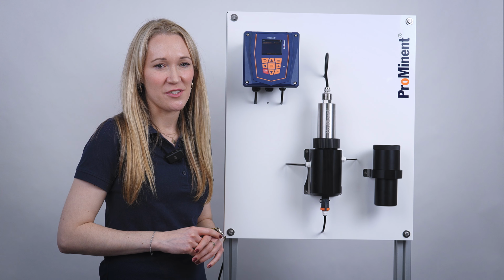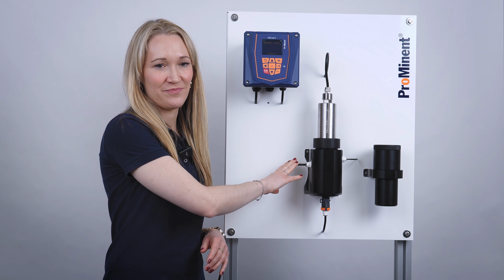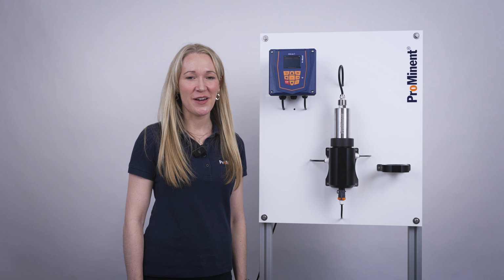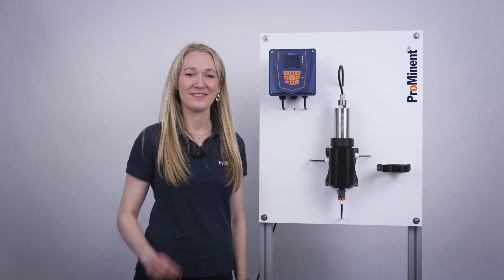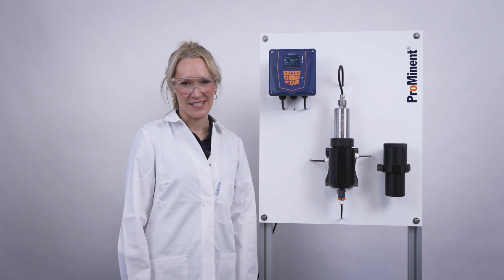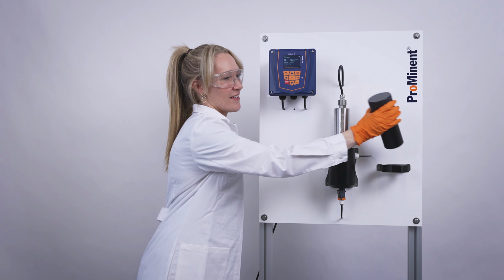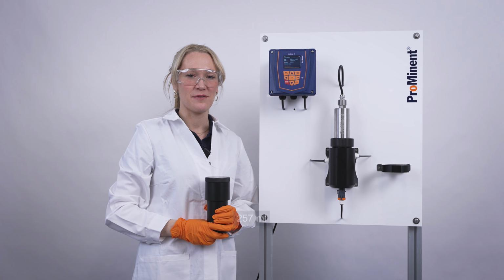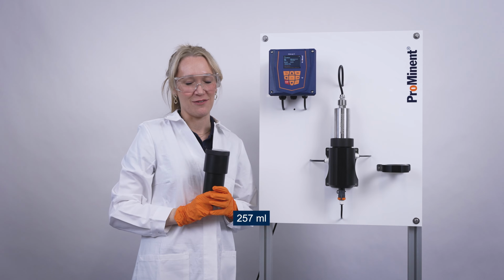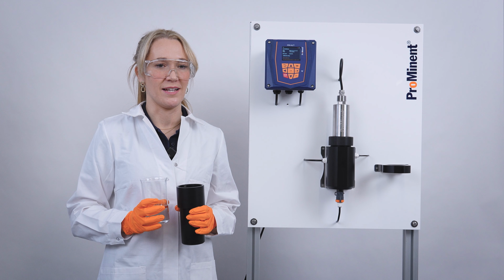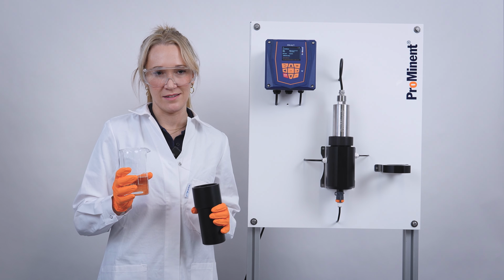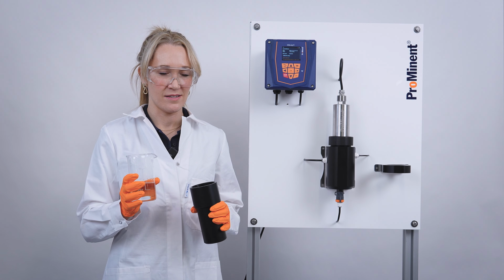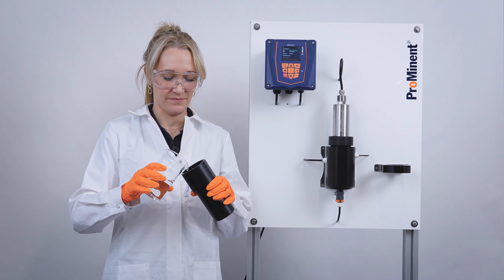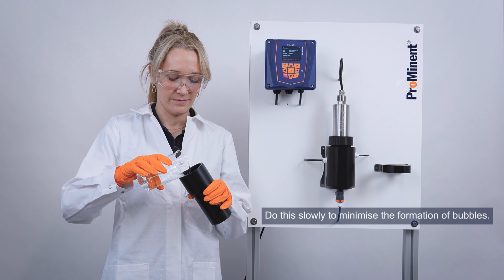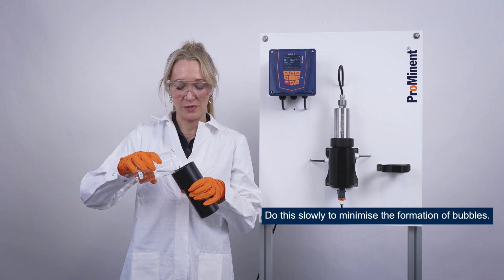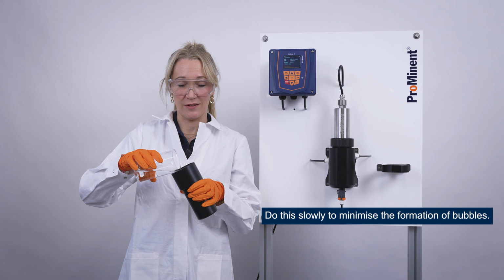Before starting the calibration, turn off the incoming flow. When calibrating this formazine, you have to wear your personal safety equipment. To calibrate the sensor, a volume of 257 milliliters is required per filling of the calibration vessel. After opening the calibration vessel, take the standard and slowly fill it inside until you reach the mark. Do this pretty slowly so that air bubbles cannot form.